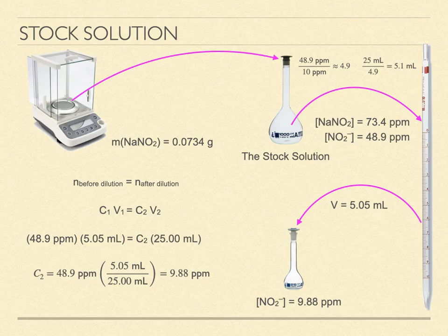We would follow this procedure, say 7 times, for concentrations that cover the target range. We would then have 7 solutions between 0.5 ppm and 20 ppm. We run each of these 3 times through the HPLC-MS, which provides an integration of the peak area for the nitrite. A number with arbitrary units is given as the magnitude of the response. A good instrument will provide a linear signal in this range. That is to say that if you graph the signal against concentration, it produces a nice straight line.